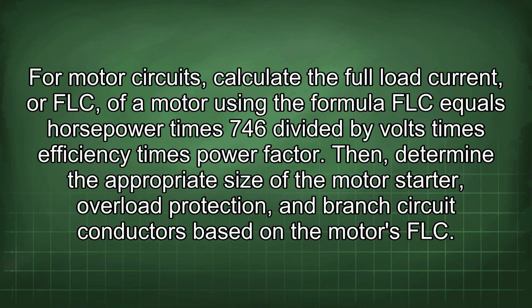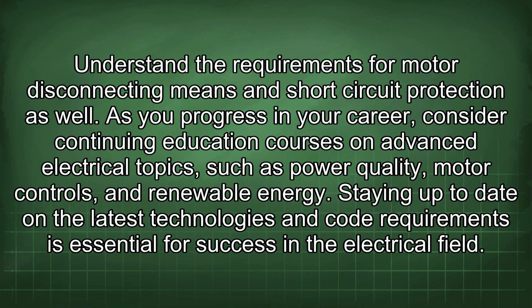For motor circuits, calculate the full load current, or FLC, for the motor using the formula FLC equals horsepower times 746 divided by volts times efficiency times power factor. Then, determine the appropriate size of the motor starter, overload protection, and branch circuit conductors based on the motor's FLC. Understand the requirements for motor disconnecting means and short circuit protection as well.